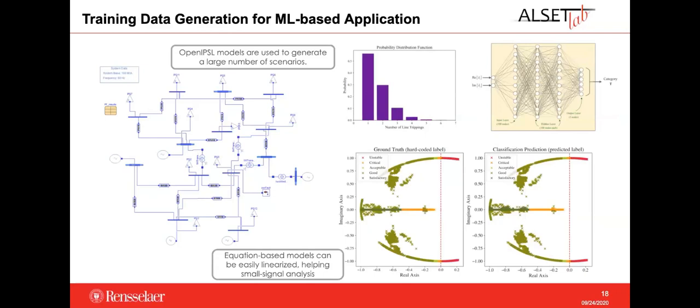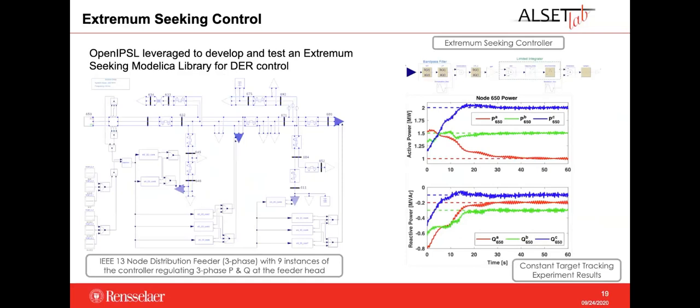In this last application, the three-phase models sub-package was used to create the IEEE 13-bus system — a distribution system containing many three-phase, two-phase, and one-phase loads, making it completely unbalanced. This network was used to test an extremum seeking controller that regulates P and Q for each phase at the feeder head. More results from this application are discussed in Maxim's publication at this very conference.